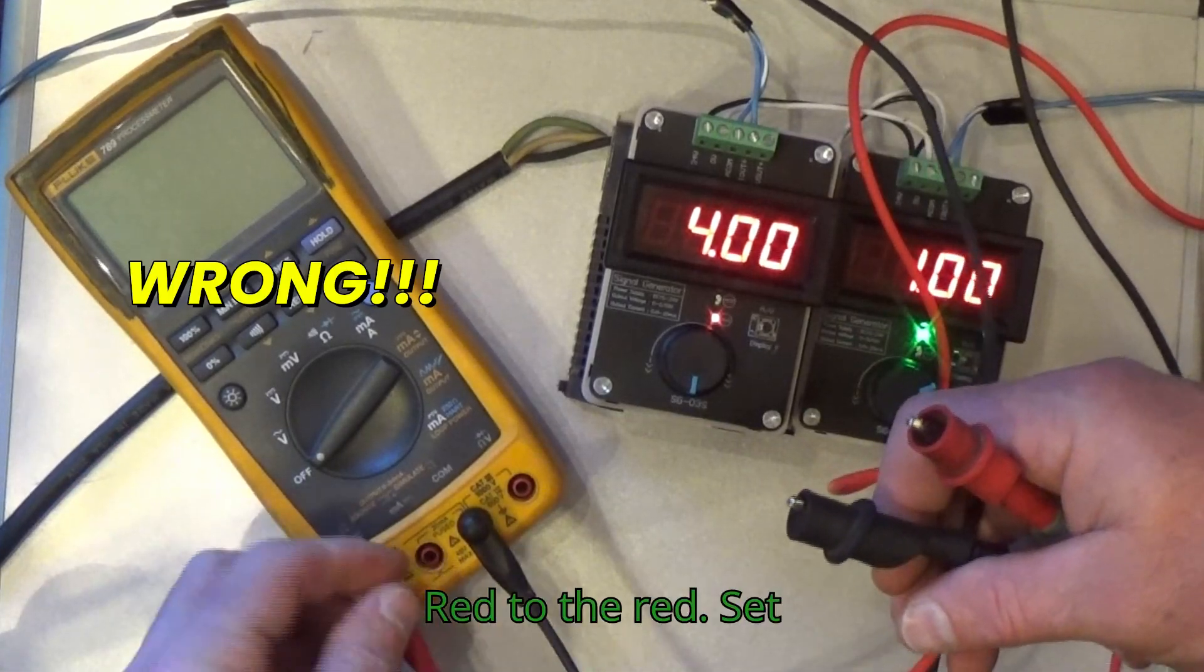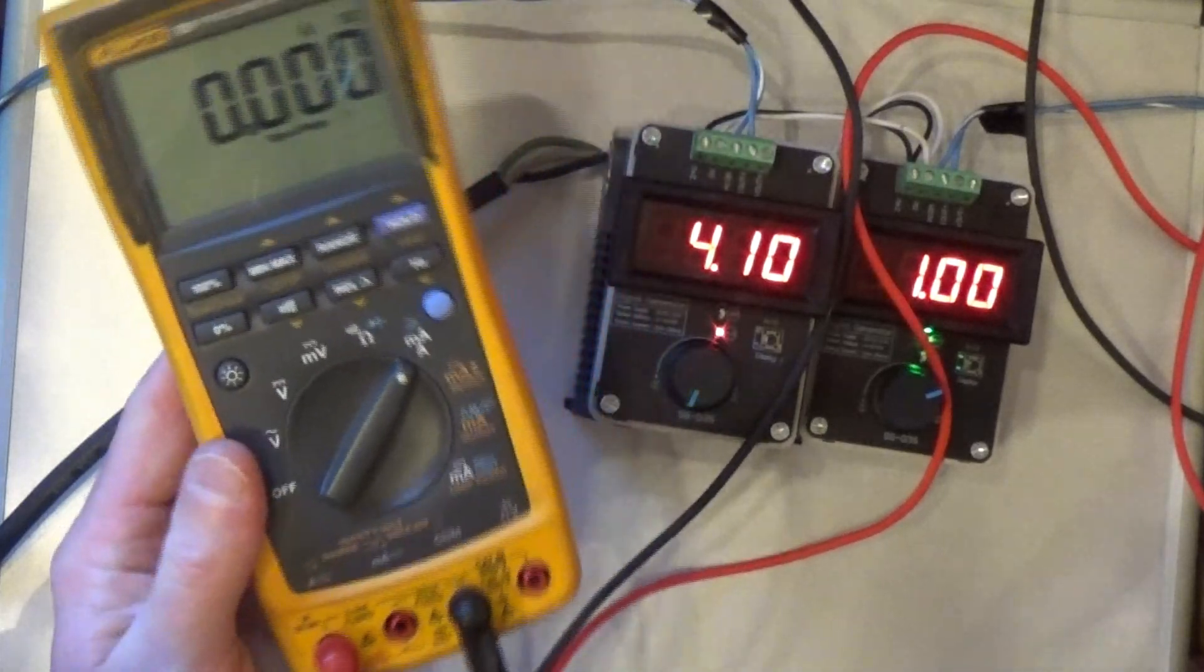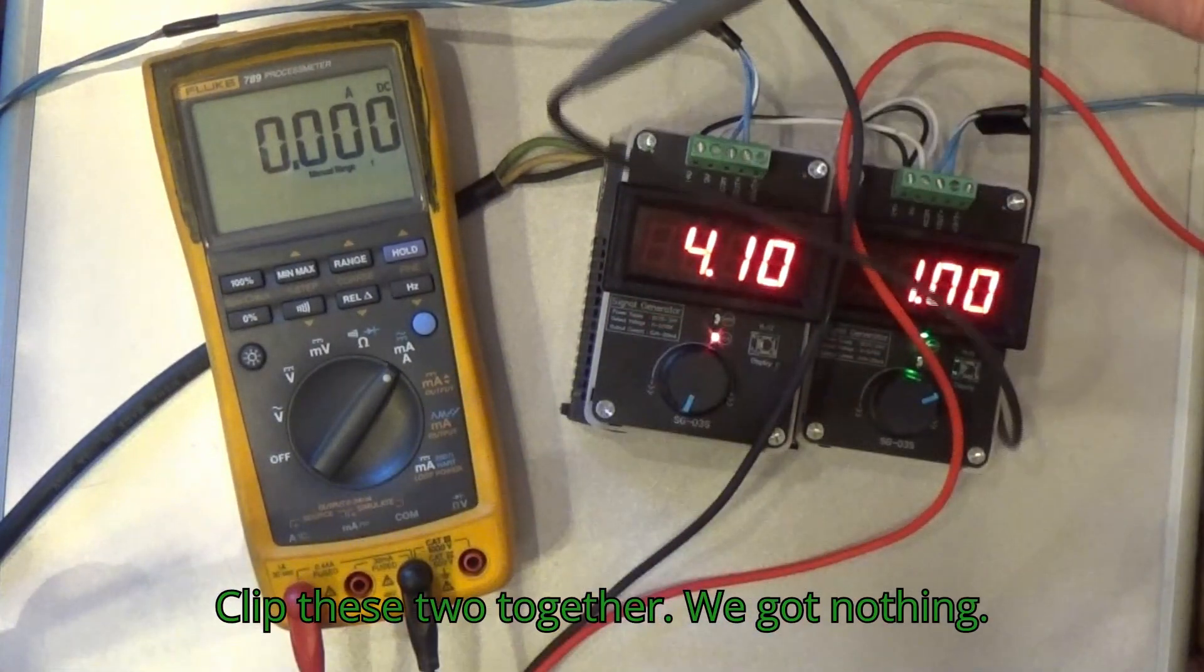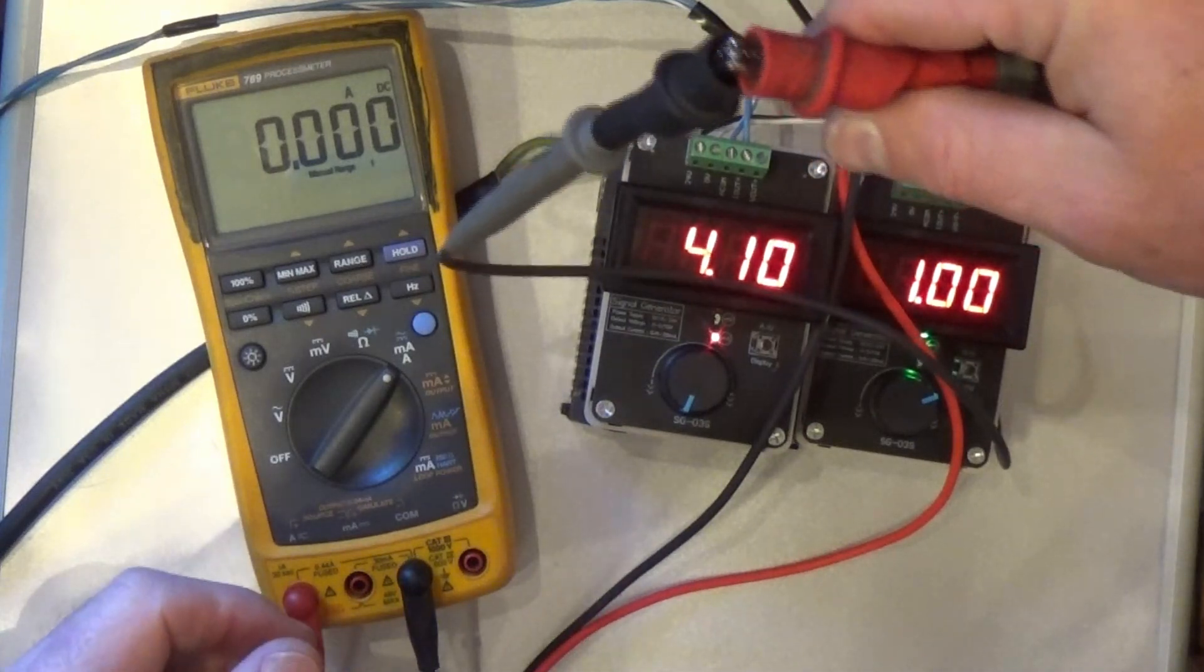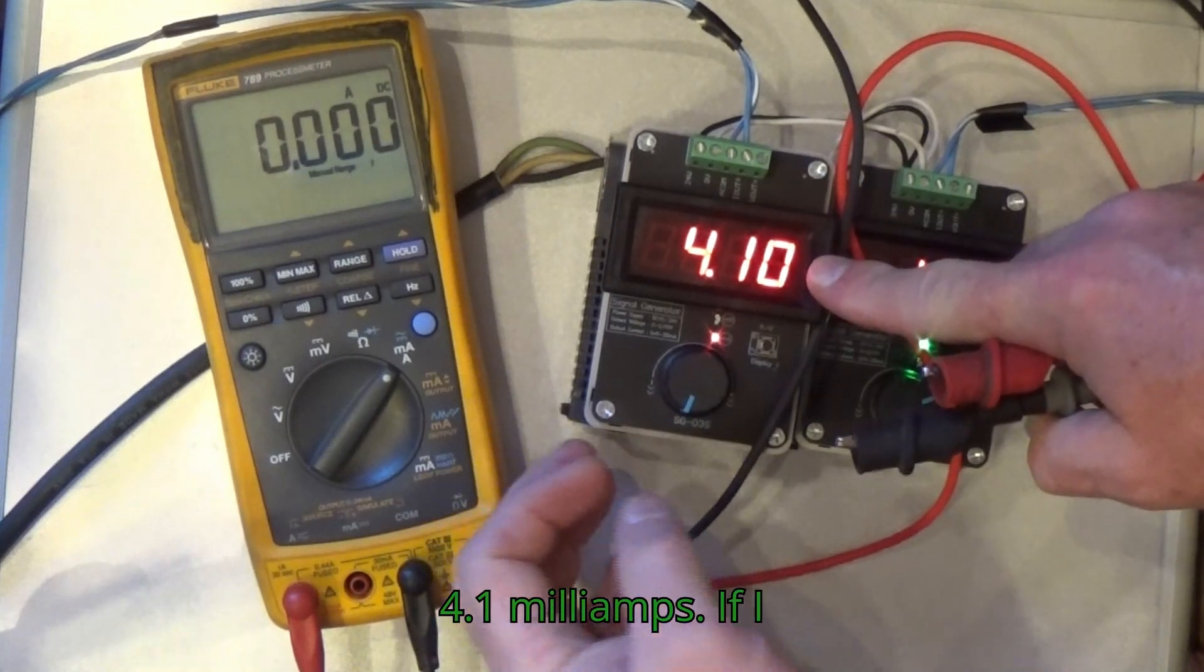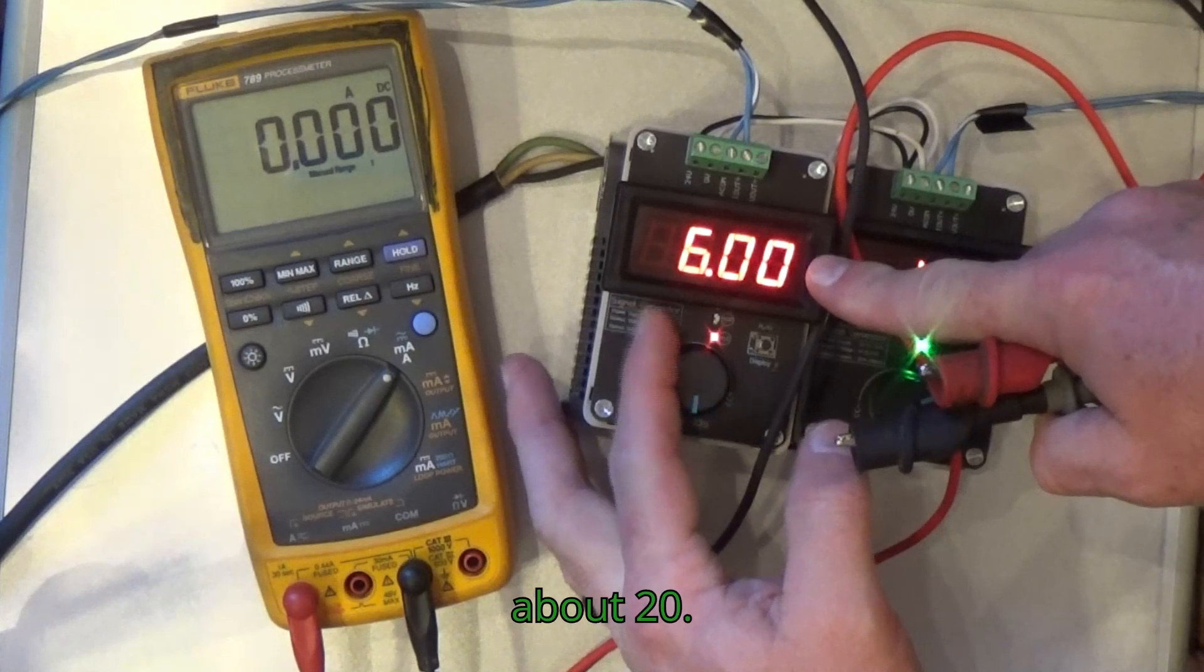Red to the red, set the dial to amps. Bring it up so you can see it a little better. Clip these two together, we got nothing. This device is generating four milliamps, 4.1 milliamps. If I rotate this dial, it'll generate up to about 20.